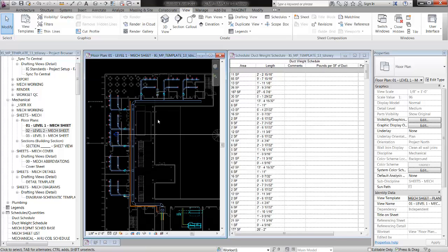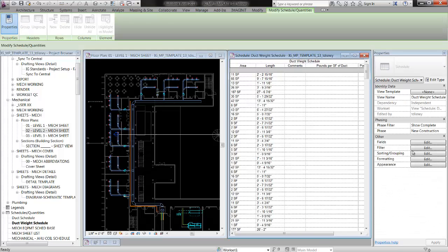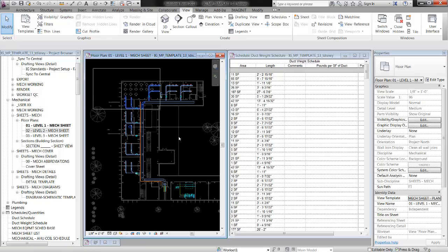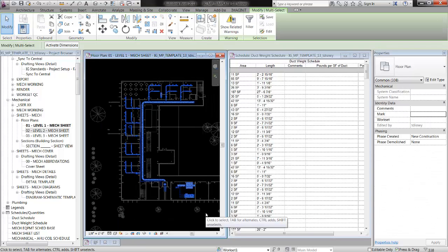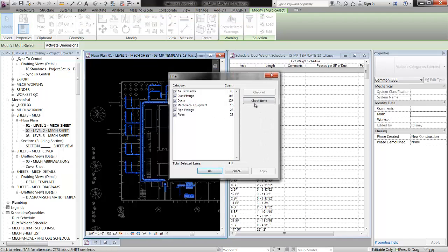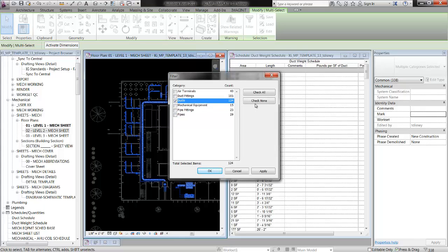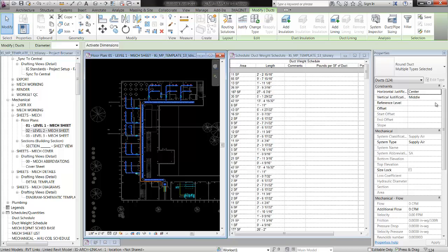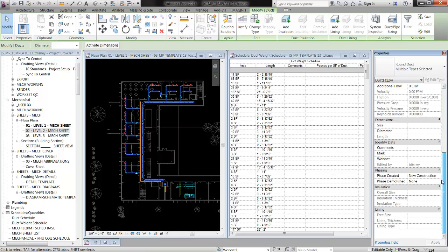Let's say I just want to know about the duct work on this level — level one. What I'm going to do is make this schedule filter by comment. To do that, I'm going to box select everything on the first floor, hit the filter button, and uncheck everything except for ducts. I've got all of these selected, so I'm going to go over to properties, comments, and add a parameter — I'm going to call it 'ductsched' for schedule.